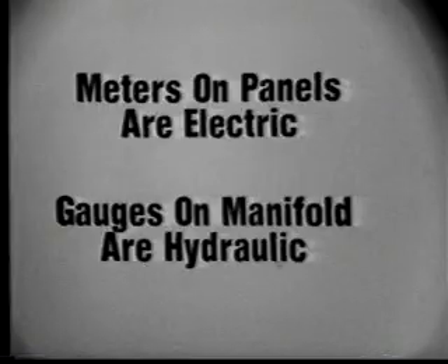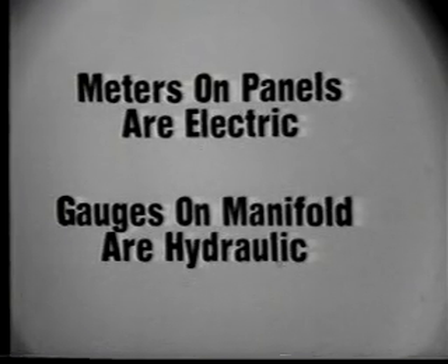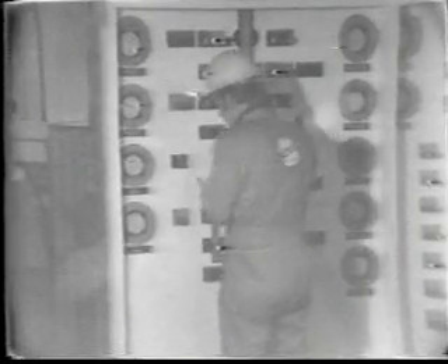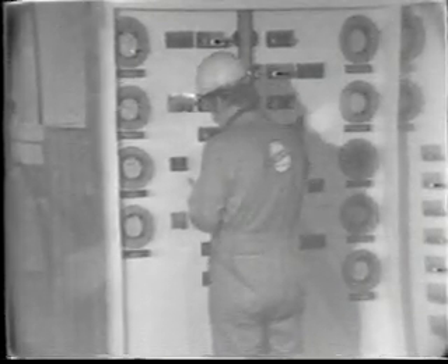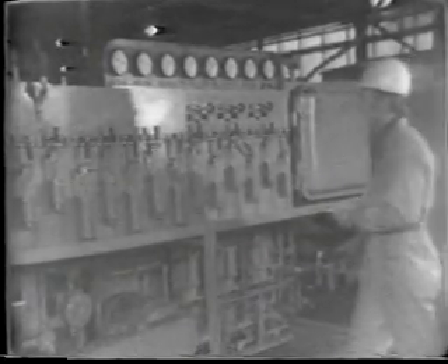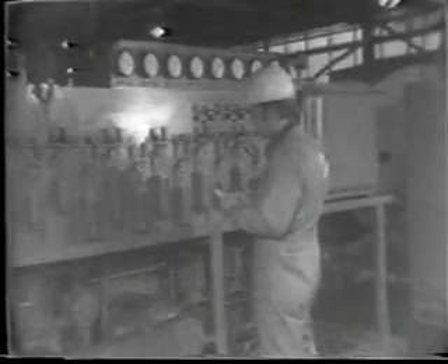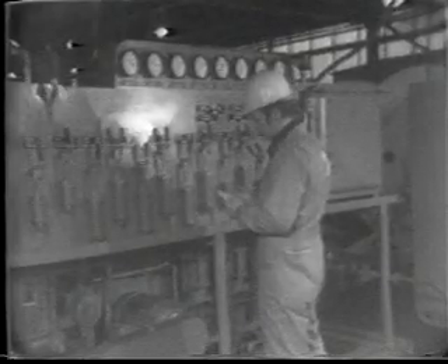Next, we'll consider meter malfunction. You should remember that the meters on the panels are electric, while the gauges on the control manifold are hydraulic. If you suspect that a meter on a panel is showing an incorrect reading, you should always first double-check it against the gauge on the hydraulic control manifold to be certain that it is faulty before you proceed to repair the meter.